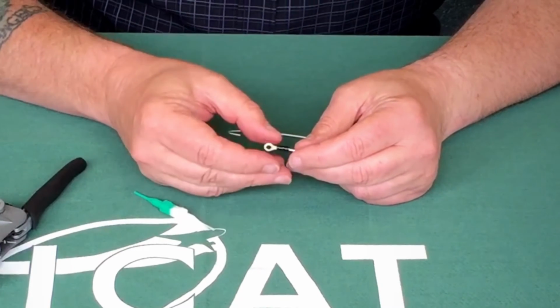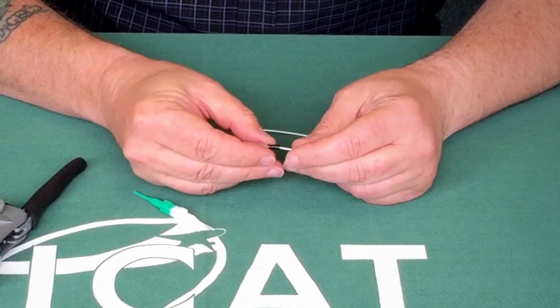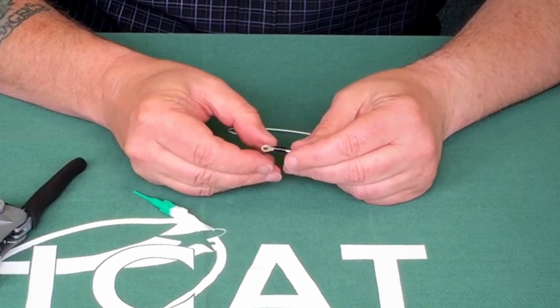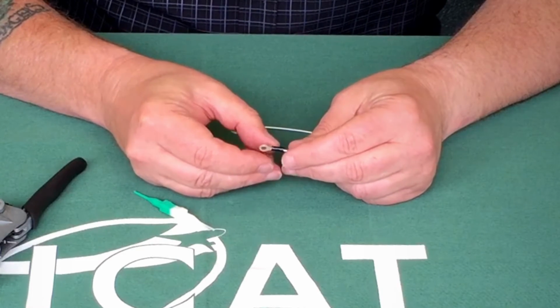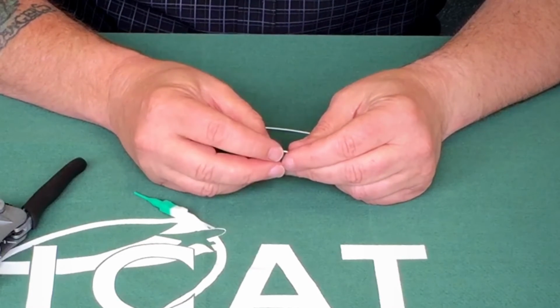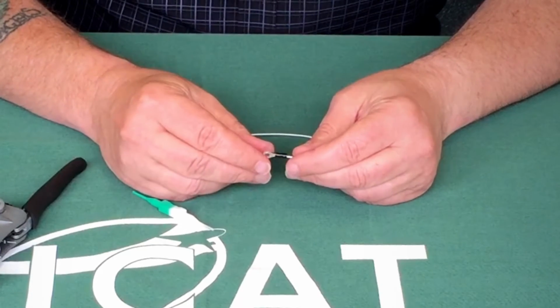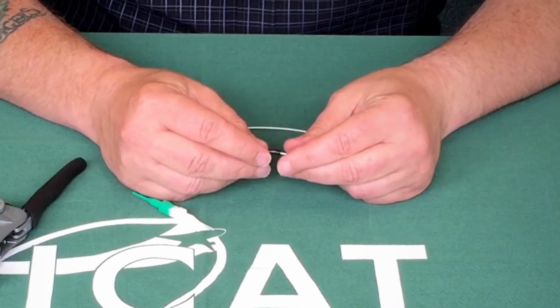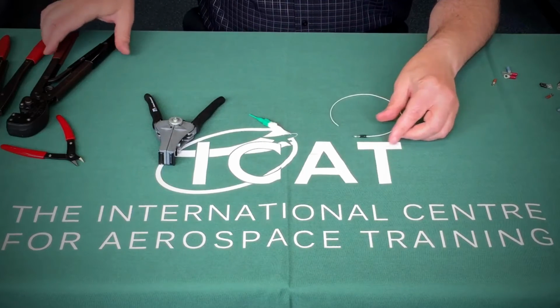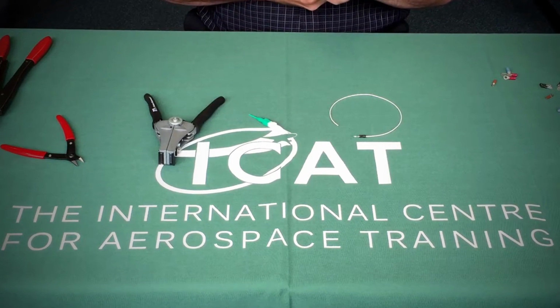As long as I can see the conductor protruding from the end of the crimp, then that should form a good enough crimp. When you fit the crimp onto the conductor, you push it on as far as you can. The insulation will back up against the butt of the crimp and the conductor should poke through. When we've done this, we then move to my crimp tool.